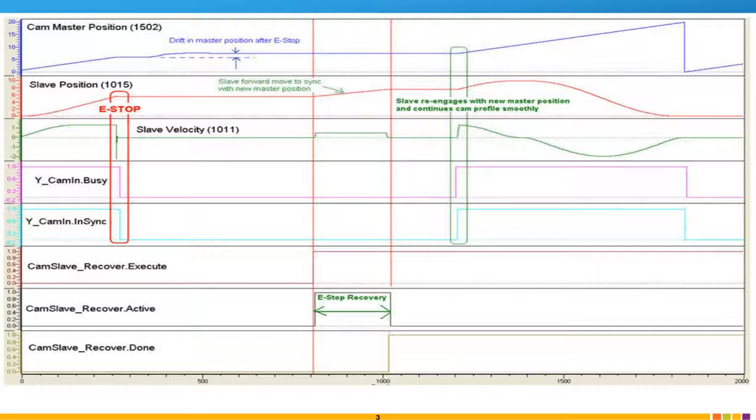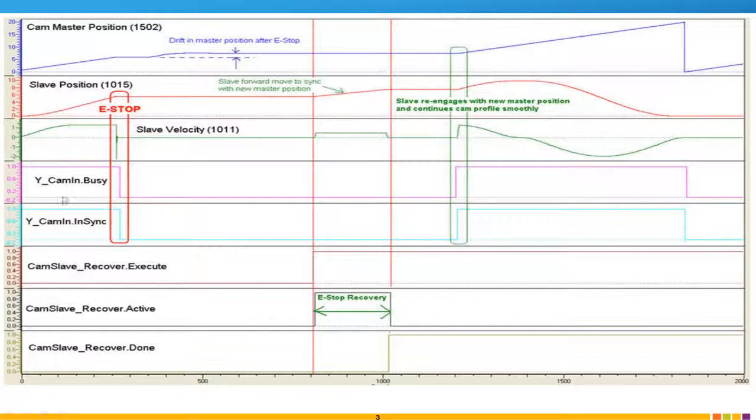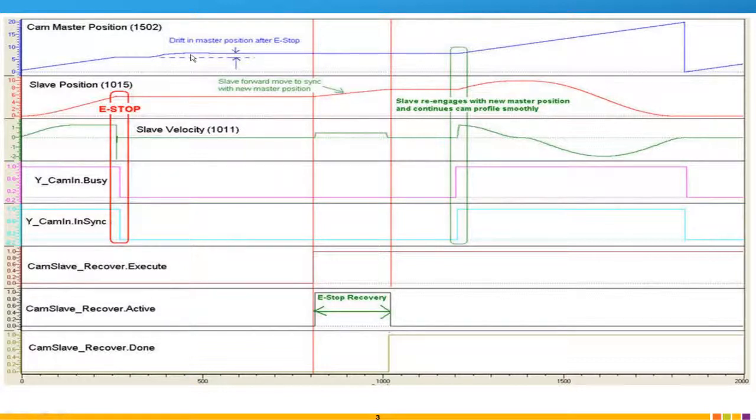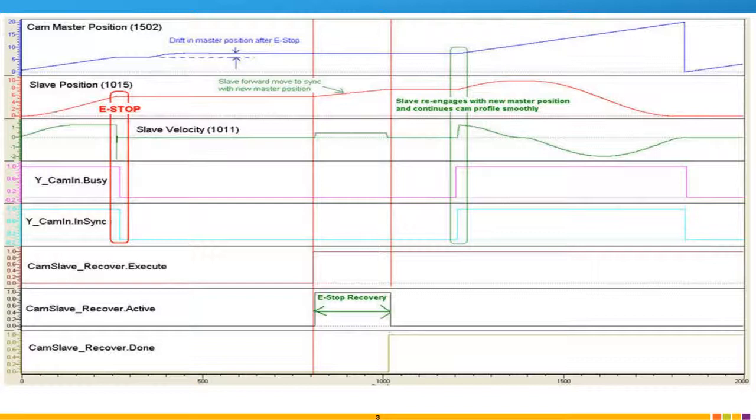All the way to the left-hand side of our trace here, you can see everything's running just fine and then all of a sudden we have an e-stop condition here. When this e-stop occurs, for whatever reason, the master continues to move. Perhaps there's a little inertial load on the master. But now we have an incongruity between our master position and our slave position. They're not in sync anymore.